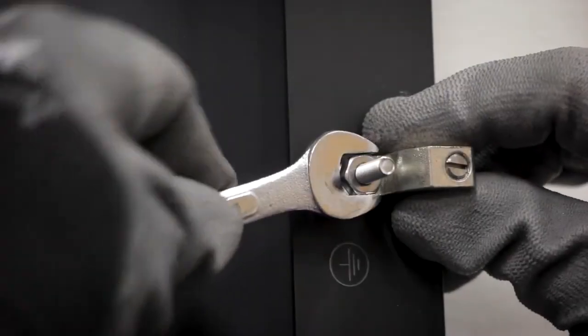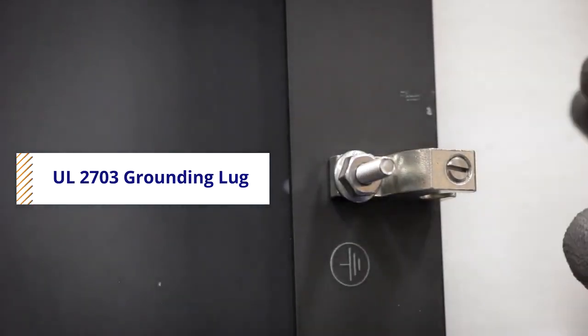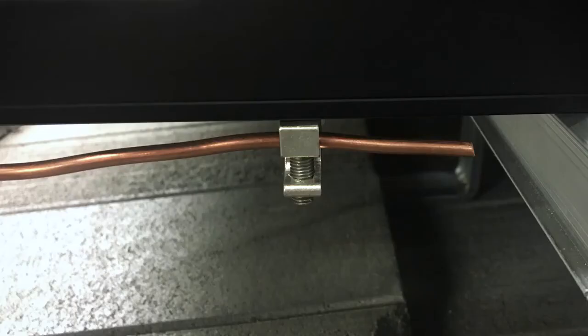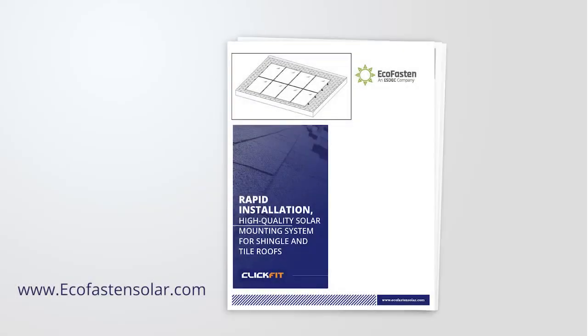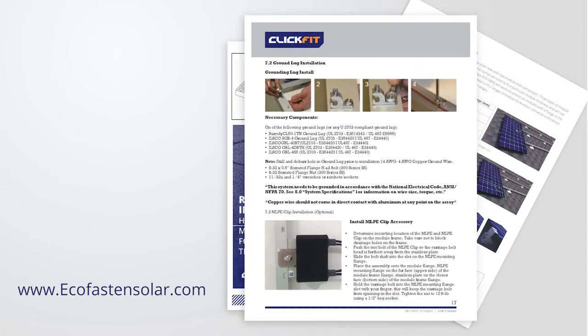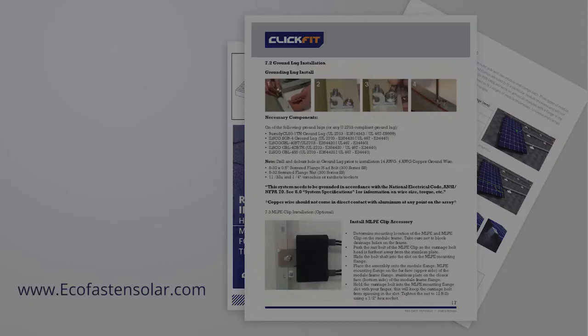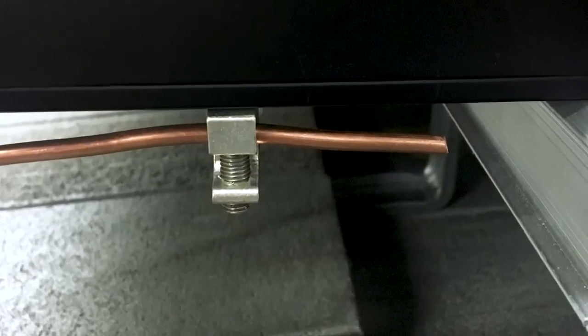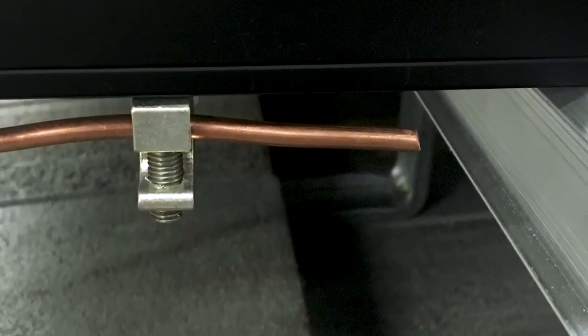easy access and inspection. To ground the system, you'll need to install a grounding lug into the flange of one of the modules in the array. One UL2703 compliant grounding lug will need to be installed for each array segment. Install the grounding lug per the grounding lug and module manufacturer's instructions. Consult the ClickFit instructional manual for specifics on approved grounding lugs, torque requirements, wire size, and NEC requirements. Copper wire should not come in direct contact with aluminum at any point on the array.